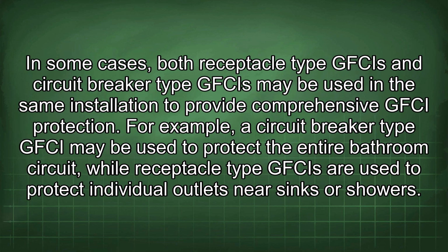In some cases, both receptacle type GFCIs and circuit breaker type GFCIs may be used in the same installation to provide comprehensive GFCI protection. For example, a circuit breaker type GFCI may be used to protect the entire bathroom circuit, while receptacle type GFCIs are used to protect individual outlets near sinks or showers.